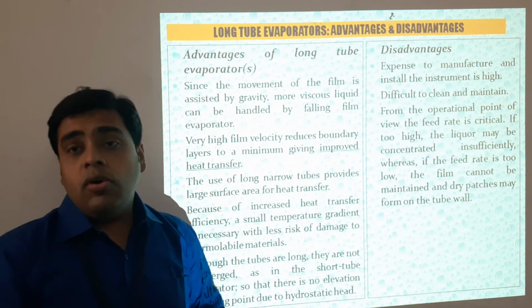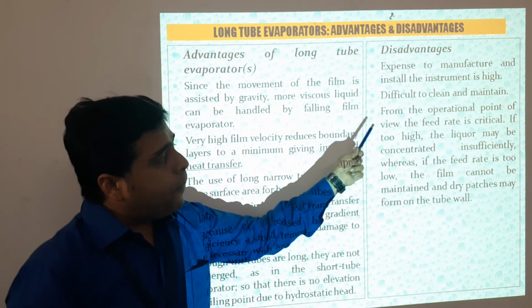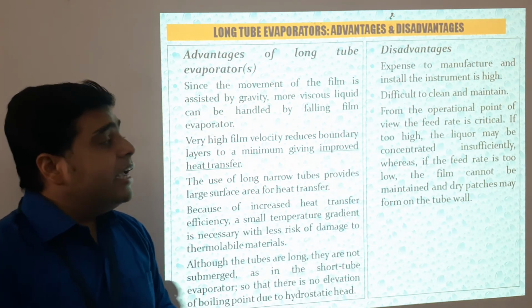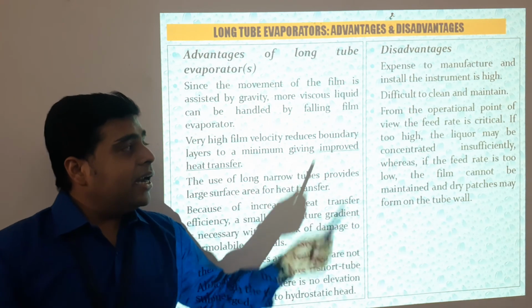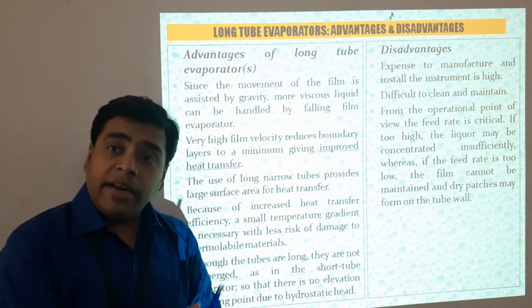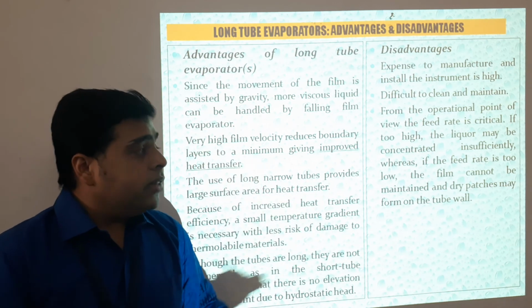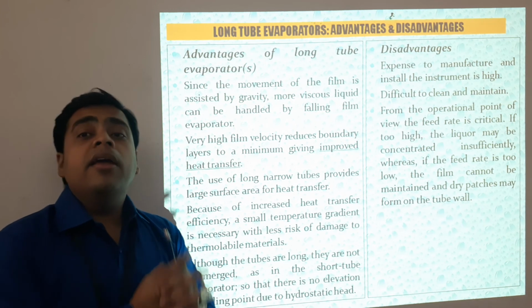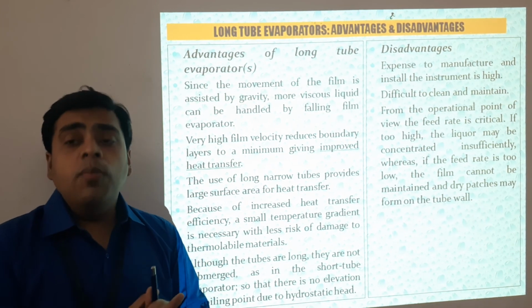So it is difficult to clean and maintain, and from the operational point of view, the feed rate is also critical. If it is too high, the liquor may be concentrated insufficiently, whereas if the feed rate is quite low, then the film cannot be maintained and dry patches may form on the tube wall.